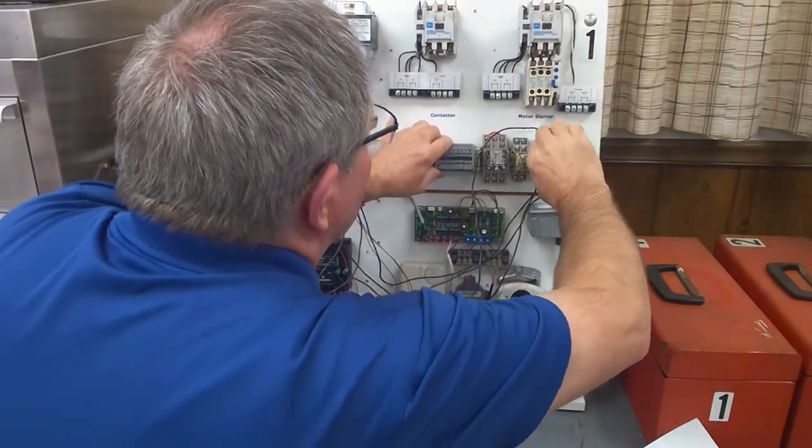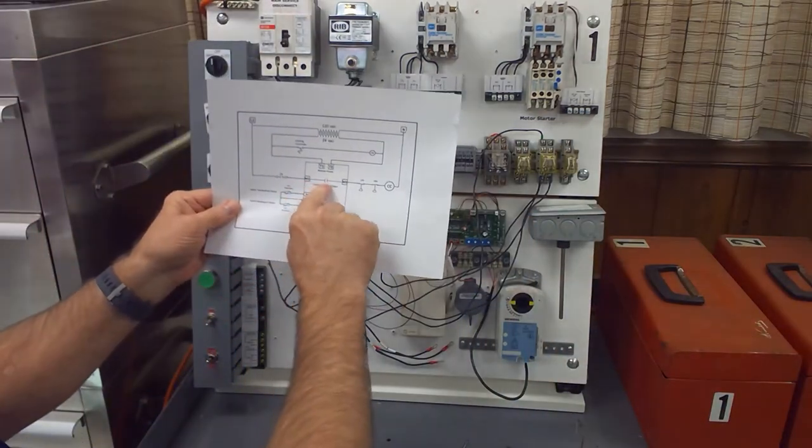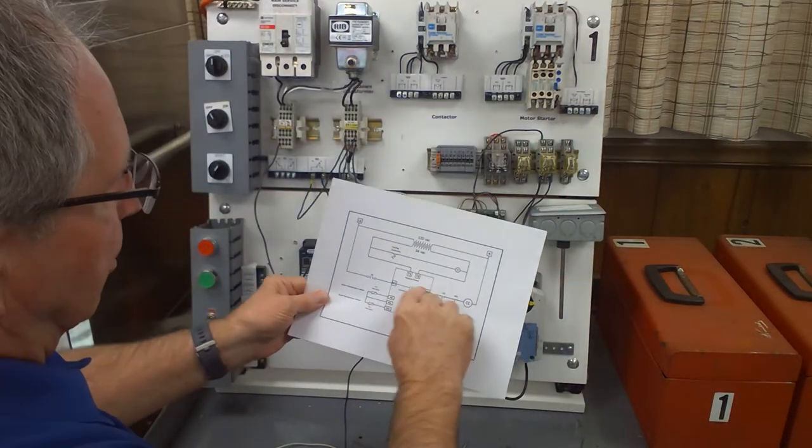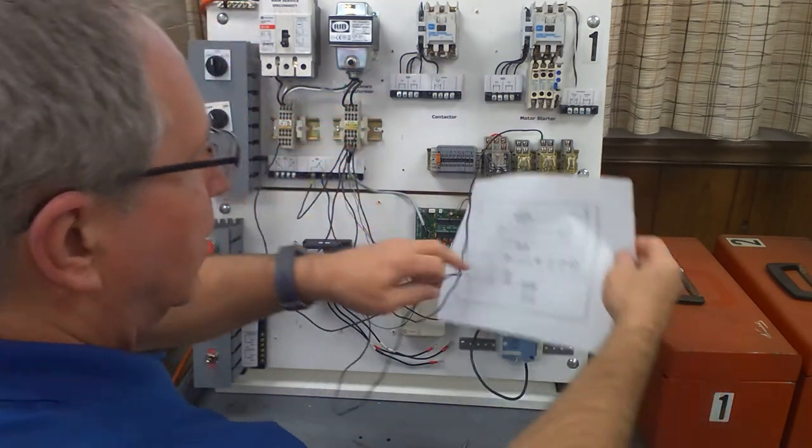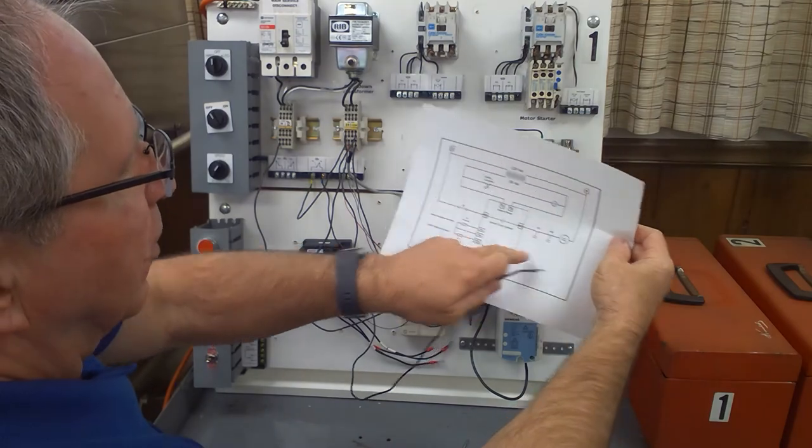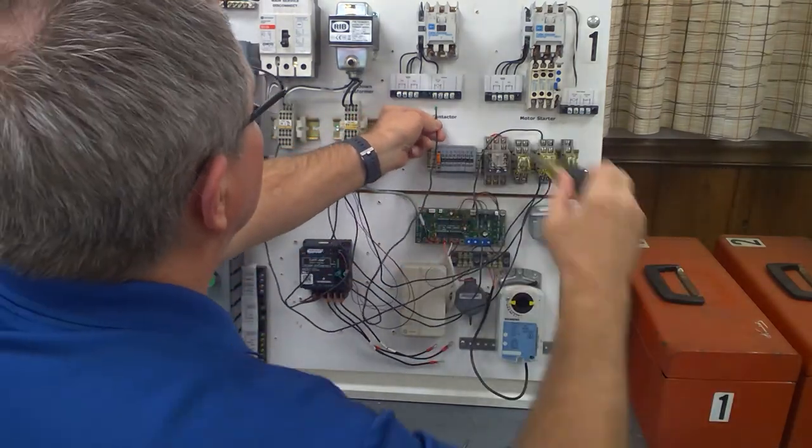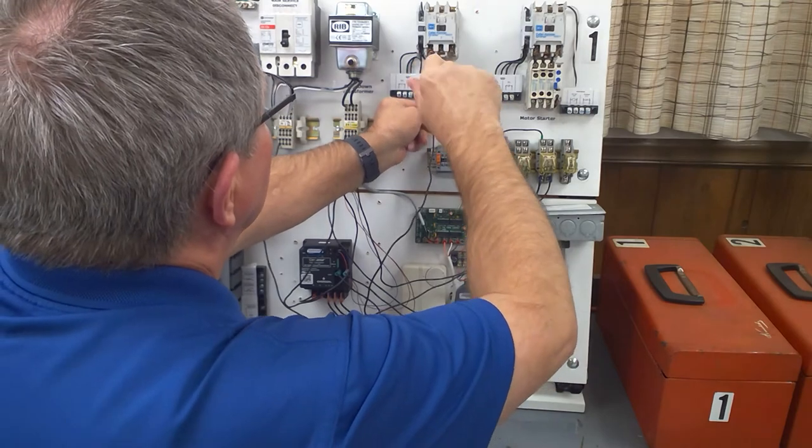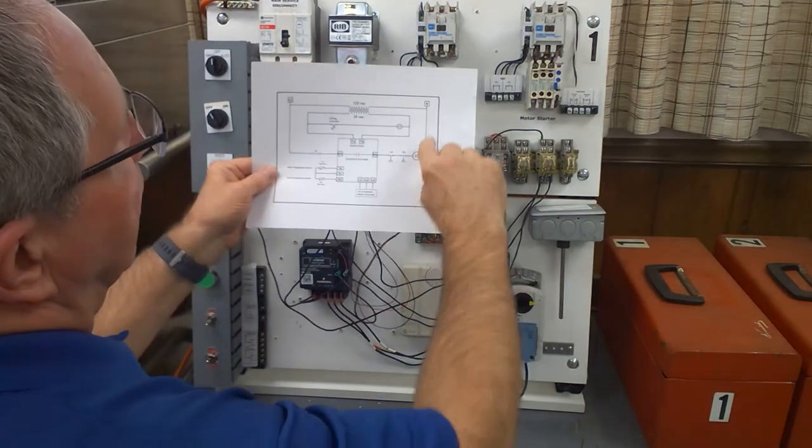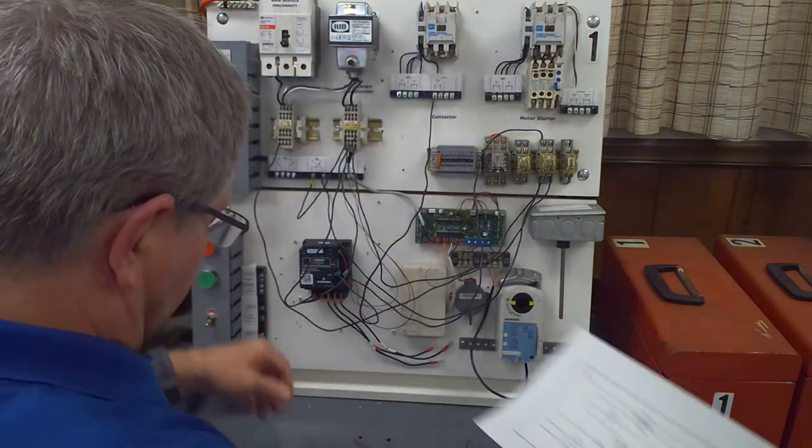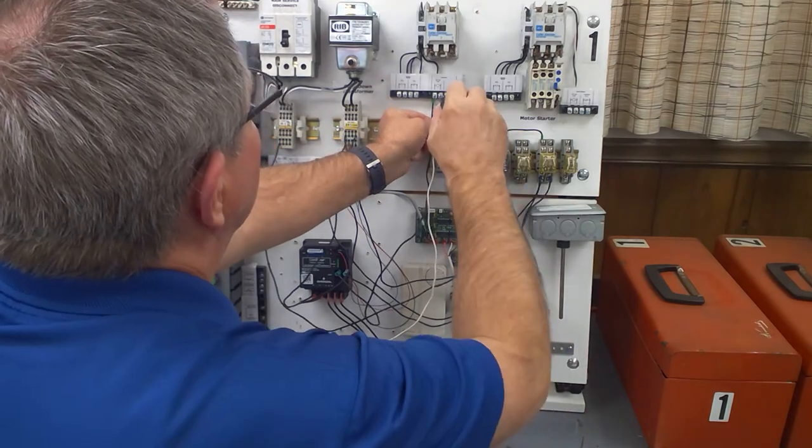Now I've got it all wired up. Coming out of the controller goes M1 to M2. This will go to the low pressure, high pressure switch, but actually I'm not going to wire that. I'm going to go directly to the contactor coil. Here is the contactor coil. And then to complete, I need to hook neutral to the opposite side of the contactor coil. Here is my white neutral, and that's going to go to my 120 volt neutral right here.